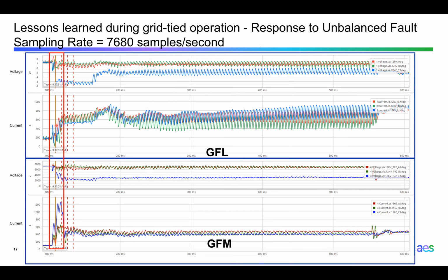But then when you start looking at the more steady state, post-transient period, even though we're still in the millisecond range or hundreds of milliseconds, the differences are pretty apparent here. Our voltage on C phase, A phase, and B phase, but more so C phase, continues to oscillate in magnitude on the faulted phase. In turn, the current is also oscillating, and you'll see that throughout the event here. It's oscillating anywhere between 400 and 800 amps of magnitude.